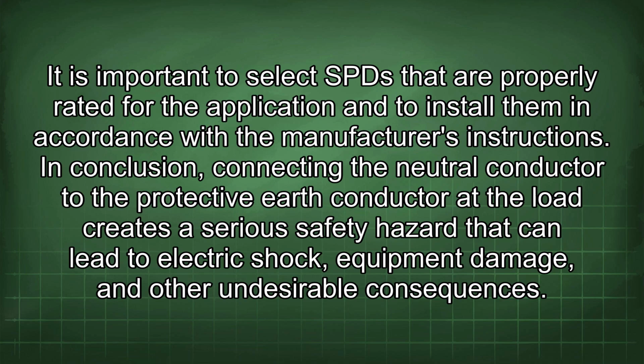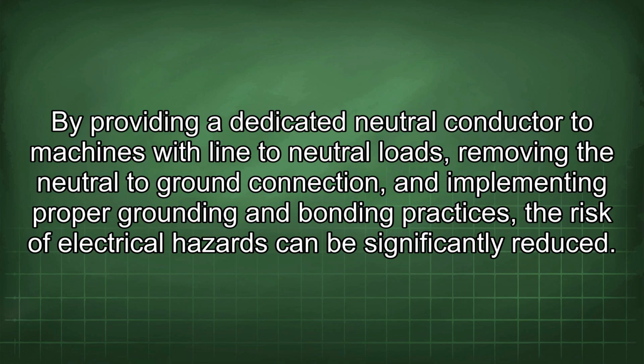the manufacturer's instructions. In conclusion, connecting the neutral conductor to the protective earth conductor at the load creates a serious safety hazard that can lead to electric shock, equipment damage, and other undesirable consequences. By providing a dedicated neutral conductor to machines with line to neutral loads, removing the neutral to ground connection, and implementing proper grounding and bonding practices, the risk of electrical hazards can be significantly reduced.